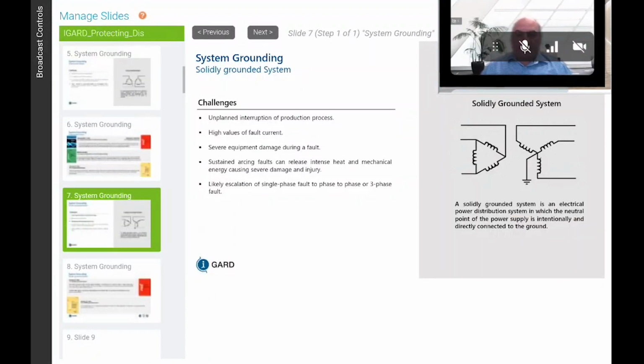So solidly grounded systems, if you look at the Y on the transformer, you have a solidly grounded link connecting directly to ground. The issue with a solidly grounded system is you have unplanned outages. So if you look at 230.95 in the National Electrical Code or 14-102 in the Canadian Electrical Code, it basically states that if you have a system that's over 150 volts to ground and greater than 1,000 amps, you must have ground fault protection.